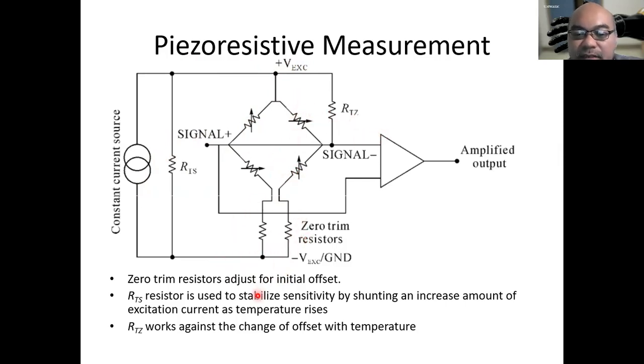So the resistance change due to temperature is also compensated. The RTZ works against the change of offset with temperature by trimming this resistor. Using either or both of these, we can zero the signal and nullify the offset due to temperature or other interference. This is the main advantage of using a Wheatstone bridge as a secondary transducer to convert resistance change from the piezoresistive device into a voltage change.